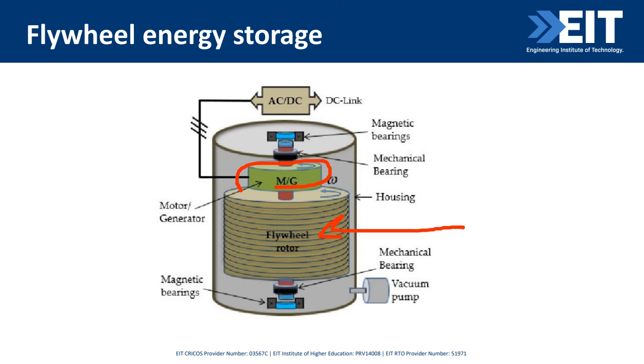That's one reason flywheels are normally installed vertically, to reduce friction. On the bottom, we have mechanical bearings with magnetic bearings that try to reduce friction on that part of the flywheel. On top, we have the motor or generator, most of the time a synchronous motor or generator, which is connected to the grid through an inverter, or an AC to DC or DC to AC converter.